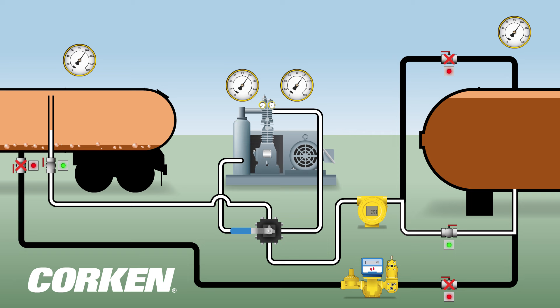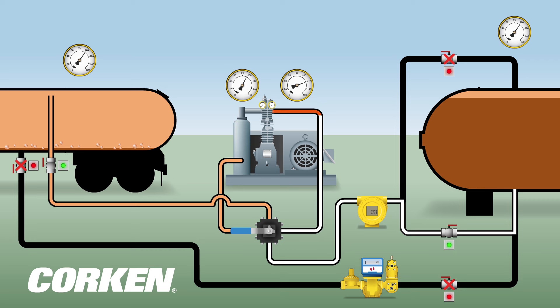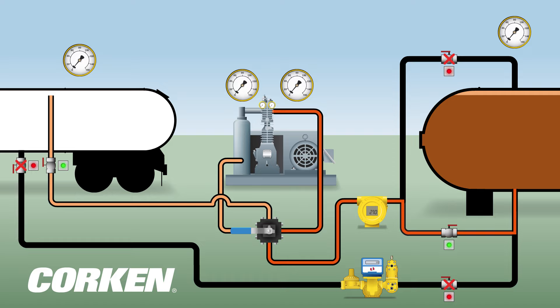The liquid heel — the remaining liquid in the transport tank — boils off during the recovery process. The compressor compresses the vapor and increases the vapor pressure as it is pushed into the bottom of the storage tank. The vapor recovery process is complete when the desired evacuation pressure is reached.